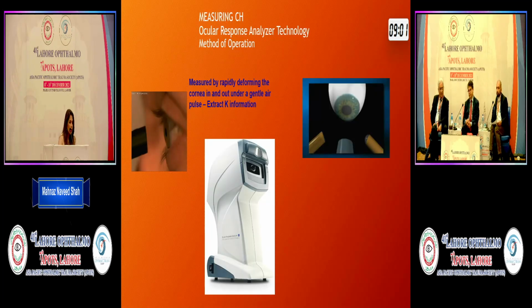How do we measure corneal hysteresis? Well, corneal hysteresis is measured by a device that is shown in the center image. This is just a tabletop device. It's very easy to operate, very portable, and the patient is seated just as if they were getting an air puff tonometry done. But here, the air puff that is used to create a pressure curve is actually not used to just generate a pressure value.